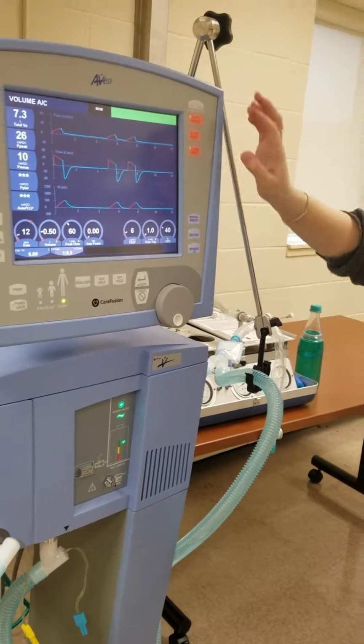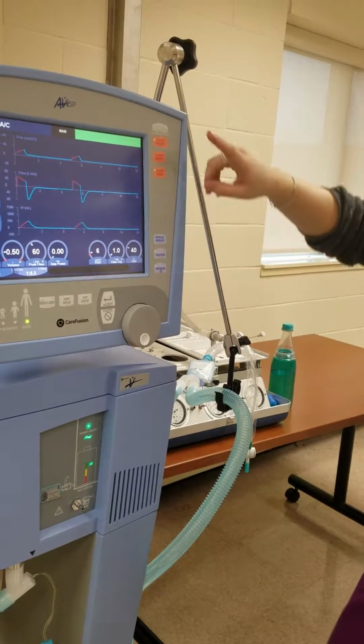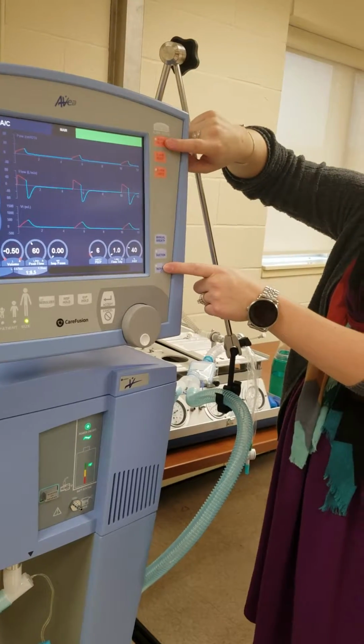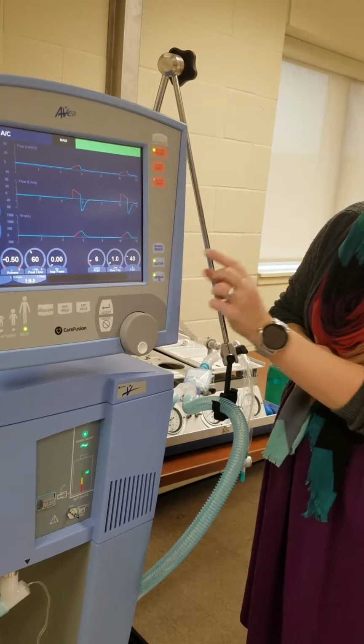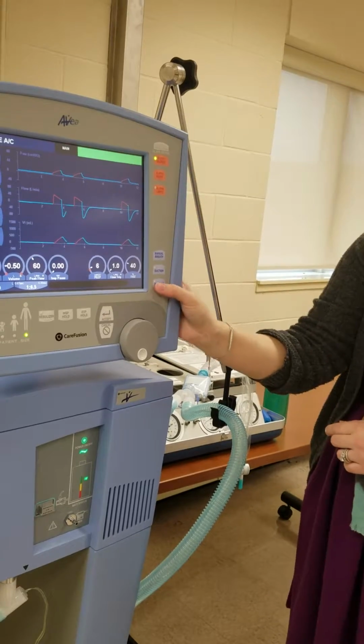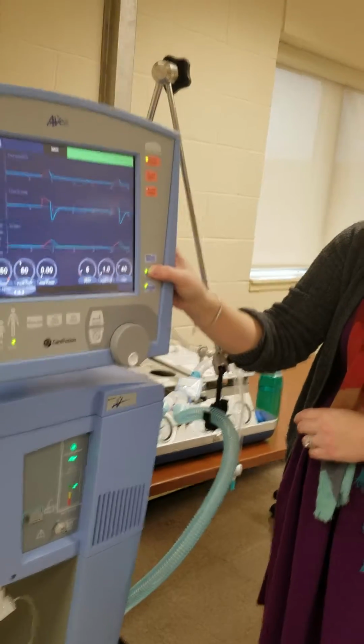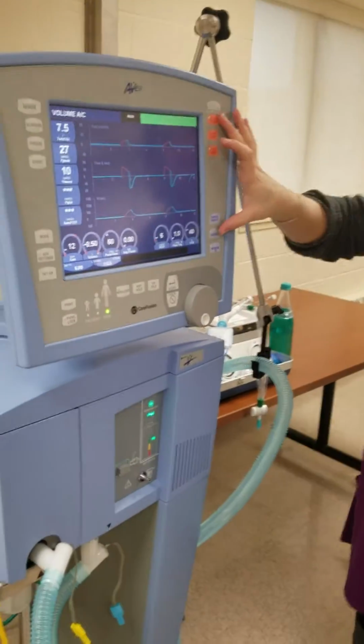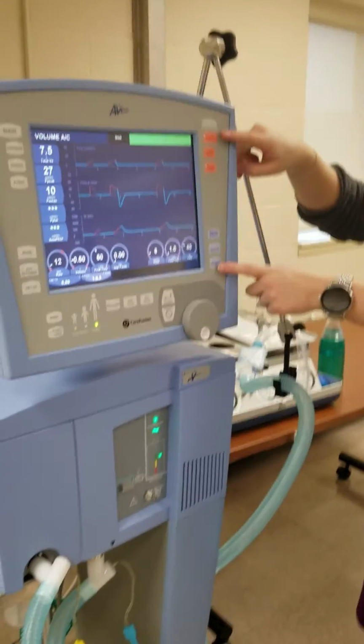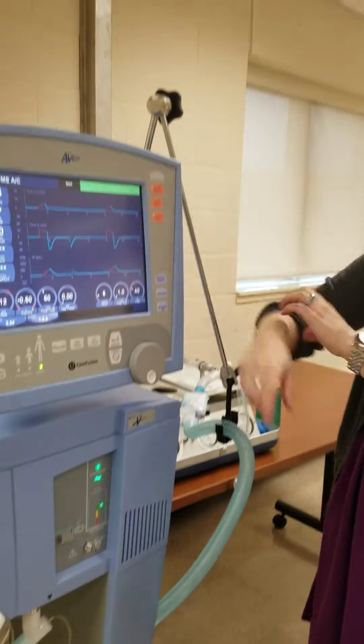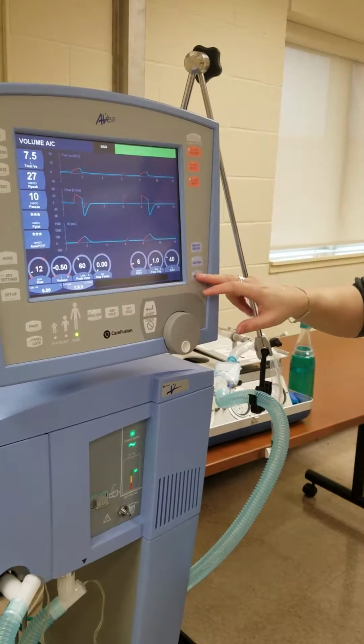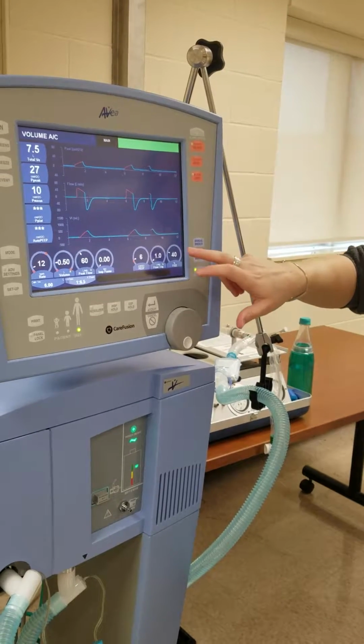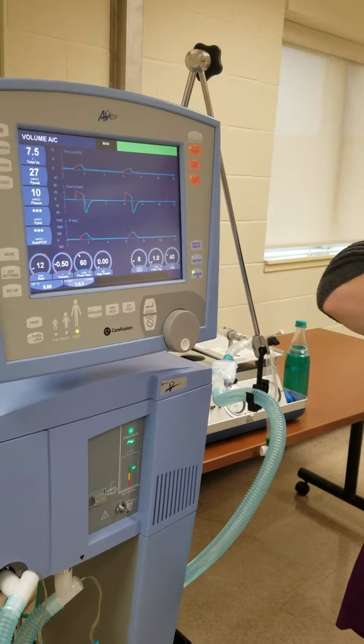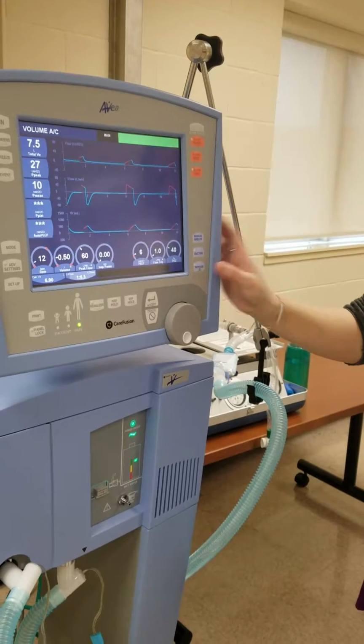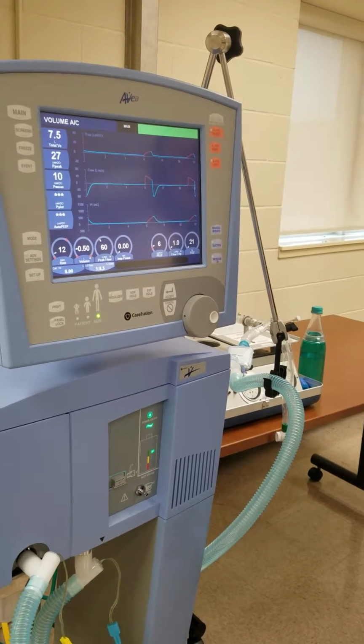This suction button, I'll show you. All this does is it hits alarm silence and increase FiO2 at the same time. So instead of coming up and saying, okay, I want silence and I want to increase O2, all you have to do is hit the button, they'll both come on at the same time. So it doesn't do anything else, it just does those two buttons at the same time. They're both a 2-minute timeout. Increase O2, you can do that on its own if you like. That'll always go up to 100% FiO2 every time for 2 minutes. I'm going to turn this down so it doesn't overlap.